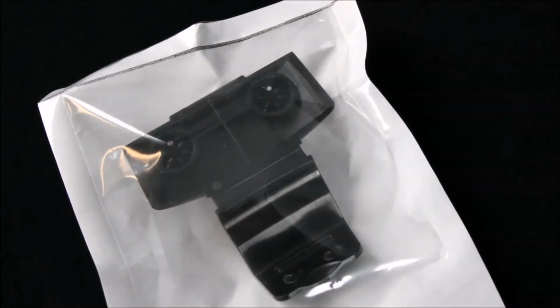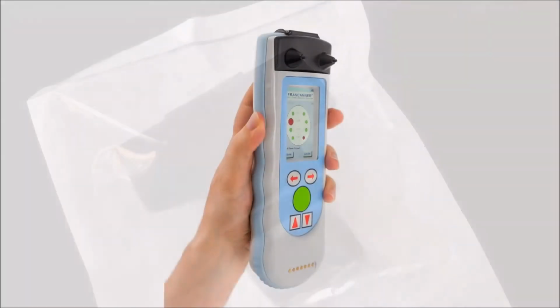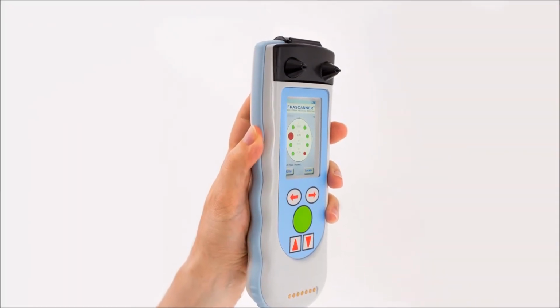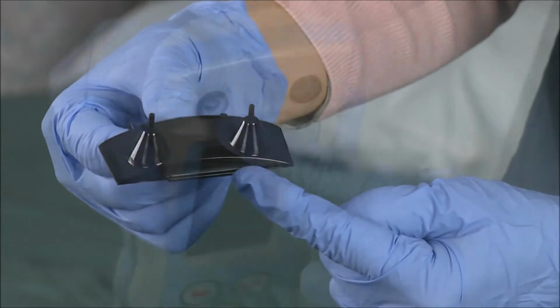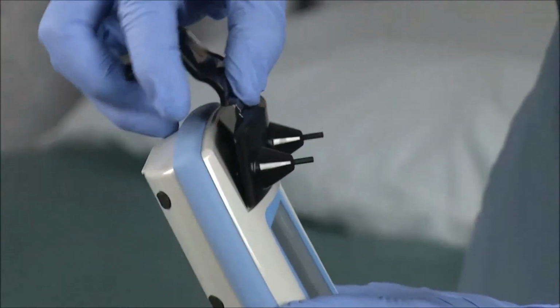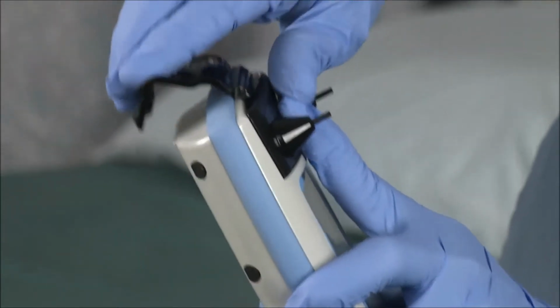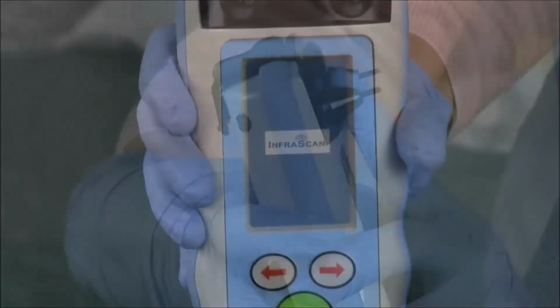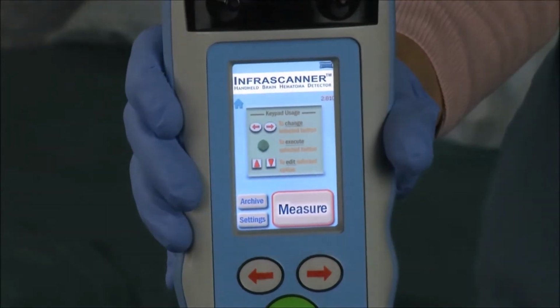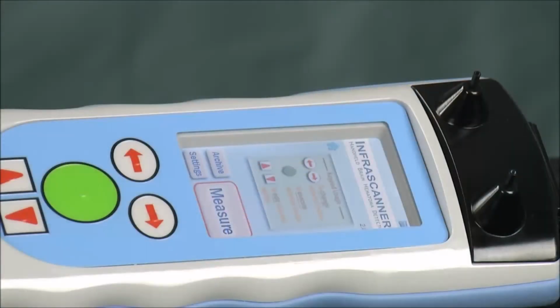A disposable fiber optic shield is required to power on the infrascanner. To install the shield, simply fit the straight edge groove into the cutout ledge on the front of the scanner and then snap the shield into place on the back side. Wait approximately 15 seconds and the unit will power up. If the shield is left on the infrascanner and the scanner is not in use, the unit will start beeping after 8 minutes to alert the user that the infrascanner's batteries are being worn down. To power off the unit, simply remove the disposable shield.